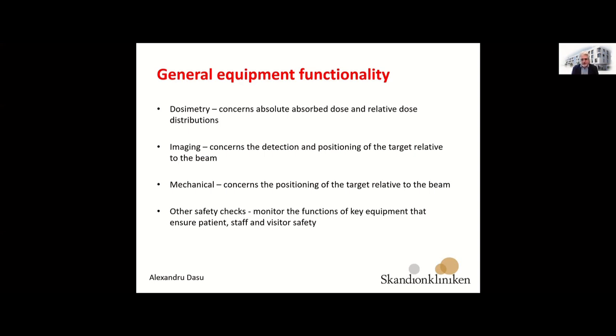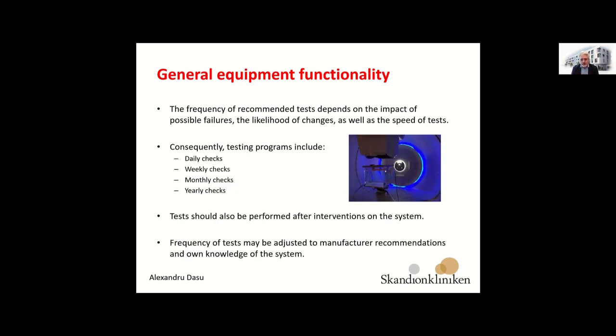And then there are the other safety checks, which are equally important, which monitor the function of key equipment that ensure patient, staff, and visitor safety. And in this, it's mainly to look at the barriers and the interlocks for the system in order not to have an unintended irradiation. Now, regarding the general equipment functionality, there are various tests, and the frequency with which one should perform the tests depends on the impact of the possible failures, the likelihood of the changes, and the speed of the test. So a test that takes 4 hours or more is not something that should be recommended for every single day, but you might still want to have some simple and quick test which would highlight the relevant parameters.